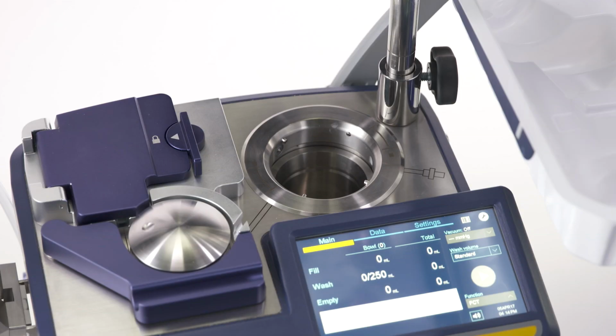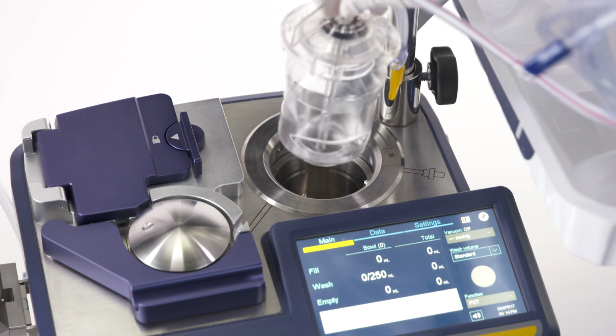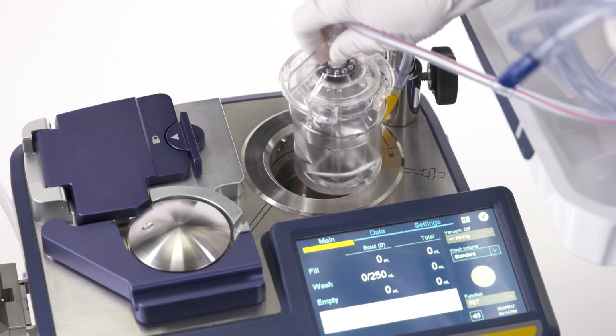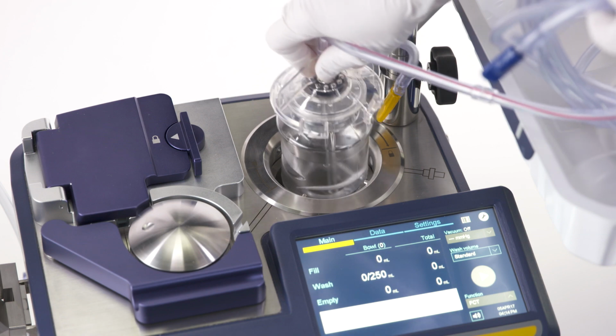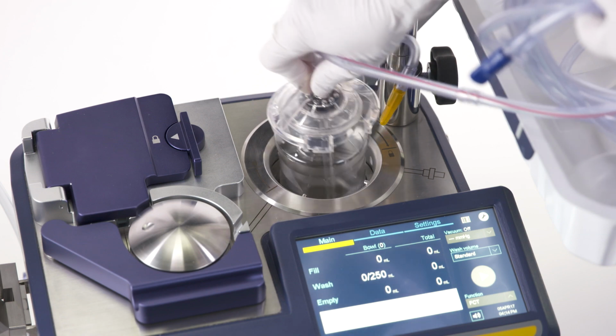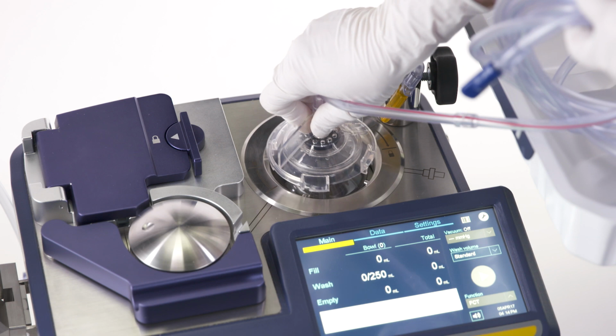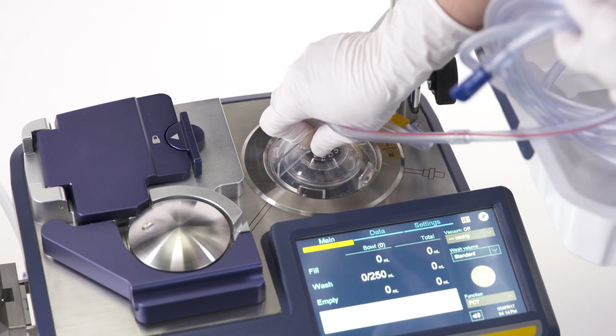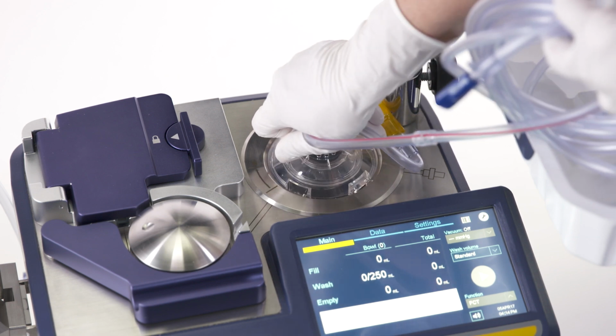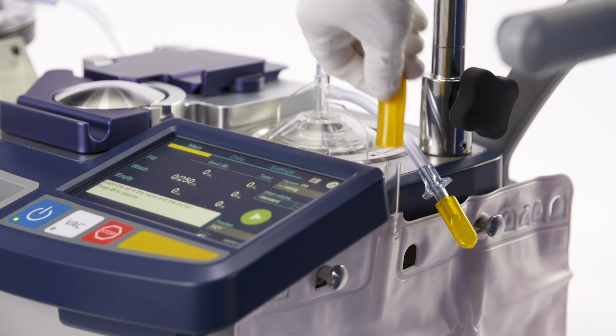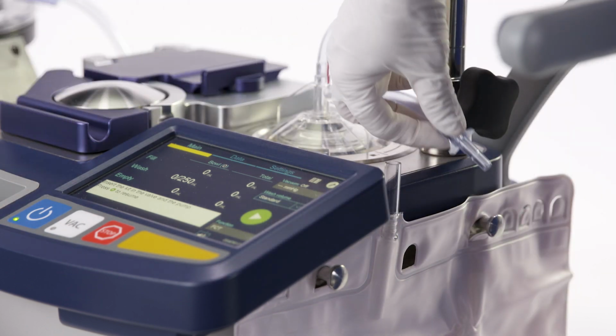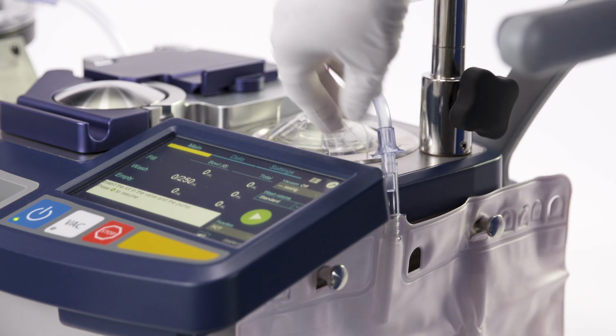Put the bowl in the centrifuge chamber with the yellow-capped waste line outlet tubing facing the waste bag. You can use the markings on the top panel as a guide. Next, align the centrifuge markings with the vertical assemblies on the bowl. Then lock the bowl by pressing down while turning the bowl clockwise until you hear a click. Go ahead and insert the yellow-capped connector into the yellow-capped inlet port on the waste bag, making sure there aren't any kinks in the waste line.